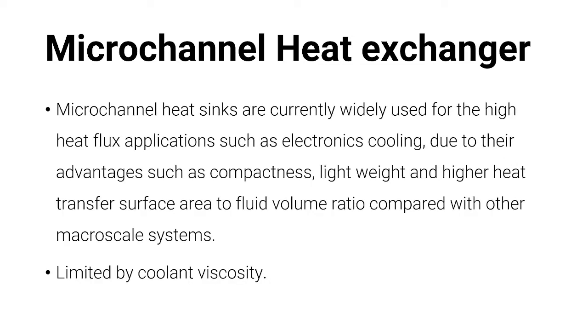Micro Channel Heat Exchangers have advantages like being compact, lightweight, and having a higher heat transfer surface area to fluid volume ratio. This ratio is one of the important factors in determining the efficiency of a heat exchanger. Since the micro channel has very small channels, it has a higher heat transfer surface area to fluid volume ratio, meaning we only have to use a small amount of fluid or refrigerant. Since not all refrigerants are environmentally friendly, we are saving nature by using Micro Channel Heat Exchangers, as only very small amounts of refrigerants are needed.